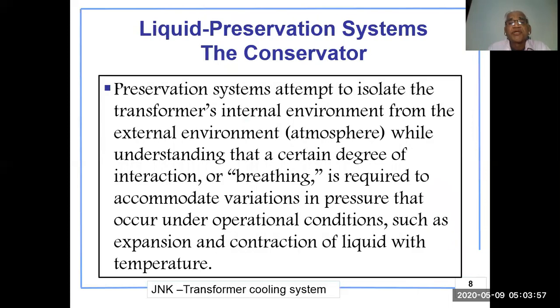The liquid preservation system is called the conservator. The preservation system isolates the transformer's internal environment from the external environment — the atmosphere — while allowing a certain degree of interaction or breathing to accommodate variations in pressure that occur under operational conditions, such as expansion and contraction of the liquid with temperature.